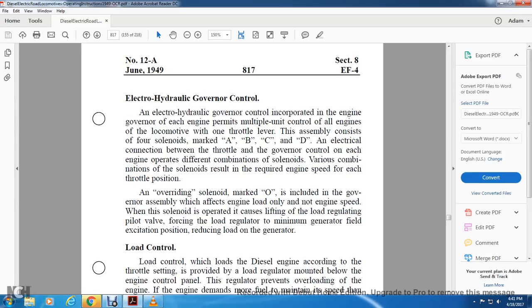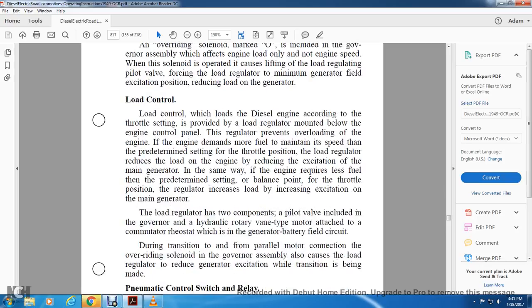The one throttle lever. This assembly consists of 4 solenoids marked A, B, C, and D, with an electrical connection between the throttle and the governor control of each engine, which operates with different combinations of the solenoids. The various combinations of the solenoids result in the required engine speed for each throttle position. An overriding solenoid marked O is included with the governor assembly, affecting the engine load only, not engine speed. When the solenoid is operated, it causes lifting of the load regulator pilot valve, forcing the load regulator to minimum generator field excitation position, reducing loading on the generator.